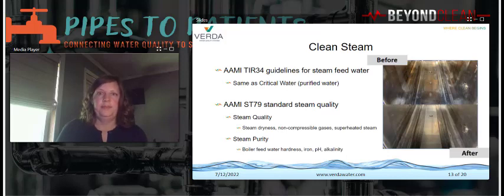Clean steam. So AAMI TIR 34 provides guidelines for necessary feed water quality for producing steam for sterile reprocessing. It's the same quality water as critical water. This can come in conflict with steam sterilizer manufacturers that require less stringent water quality parameters for their equipment to operate and to generate steam.